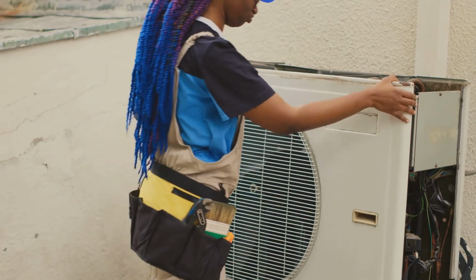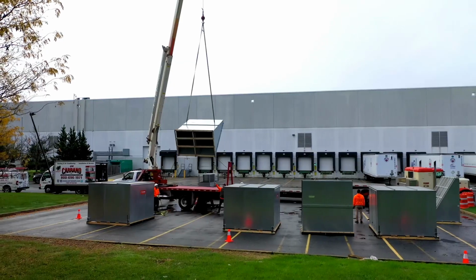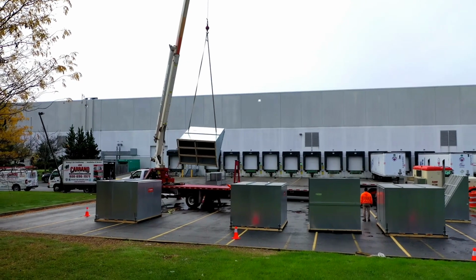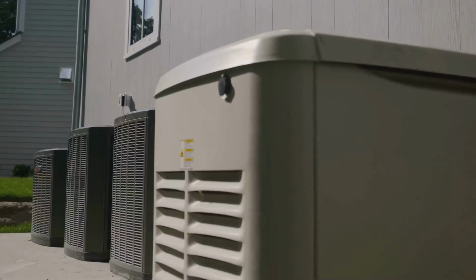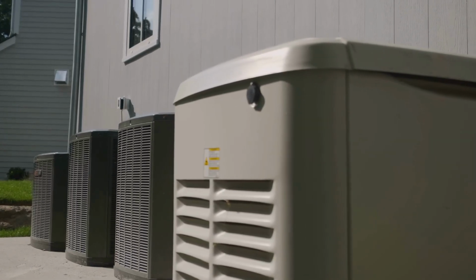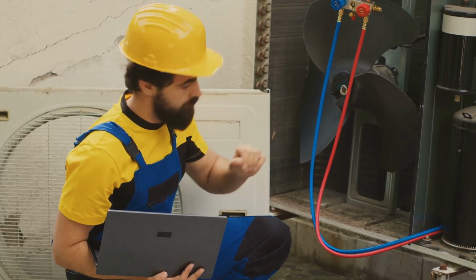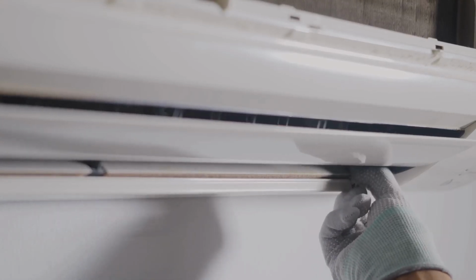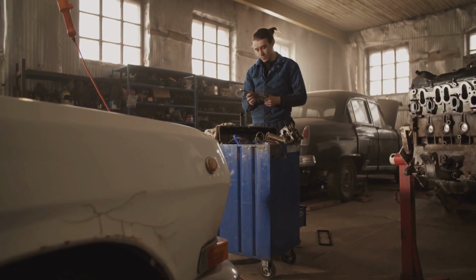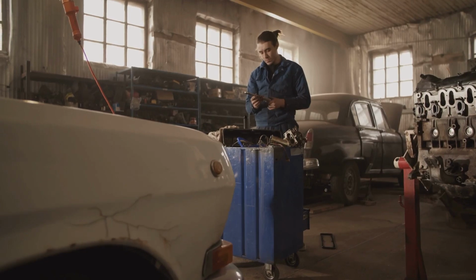Step 2. Set the outdoor unit. Carefully lift and position the outdoor unit on the prepared pad. Be sure the unit is level and secure it to the pad using the provided hardware or concrete anchors. Step 3. Connect the refrigerant lines. Connect the refrigerant lines from the indoor unit to the outdoor unit, ensuring a tight seal to prevent any leaks. Again, use a torque wrench to tighten the fittings to the manufacturer's specifications.